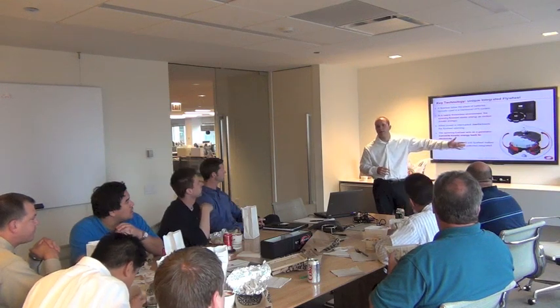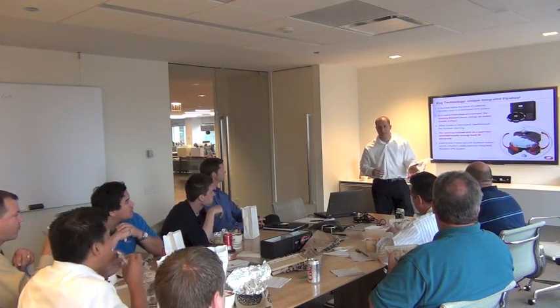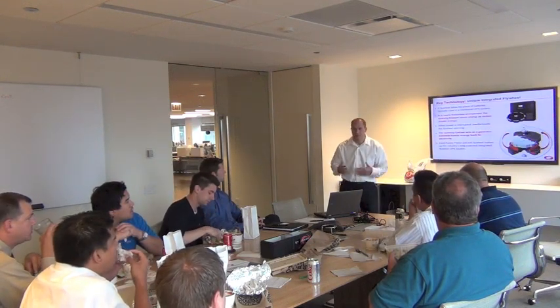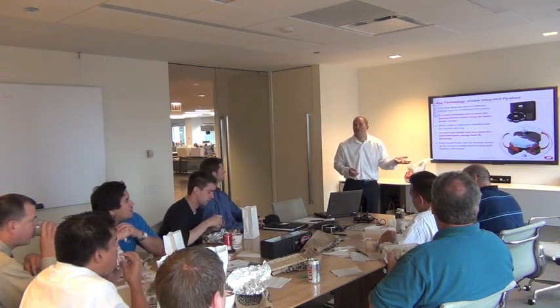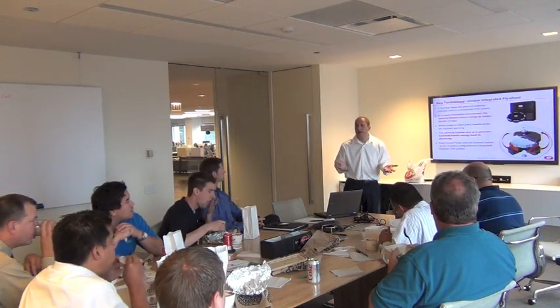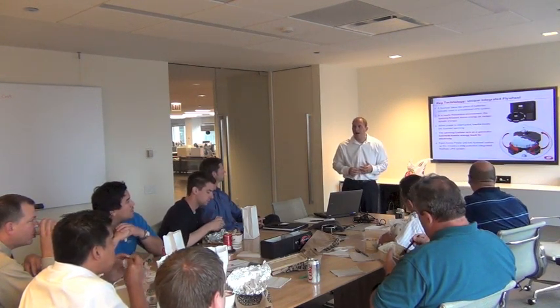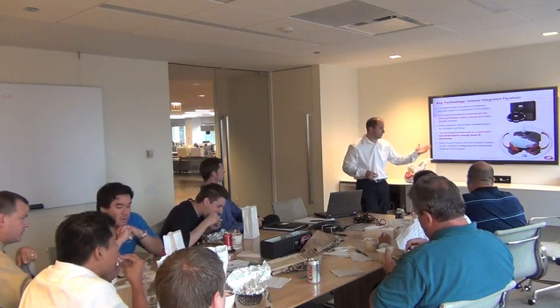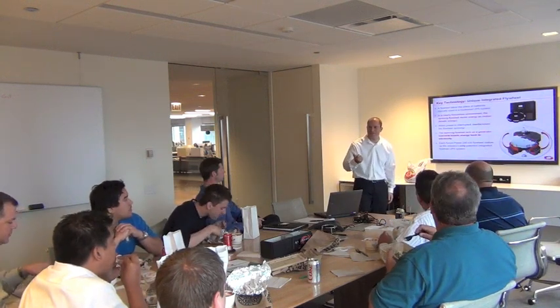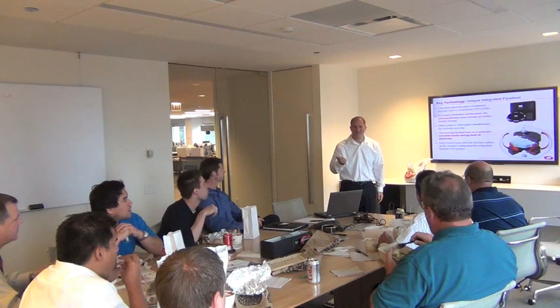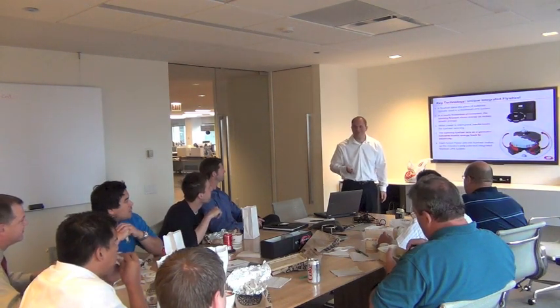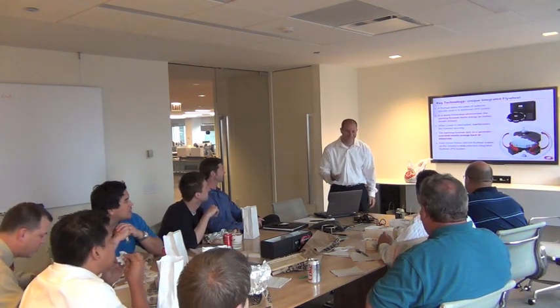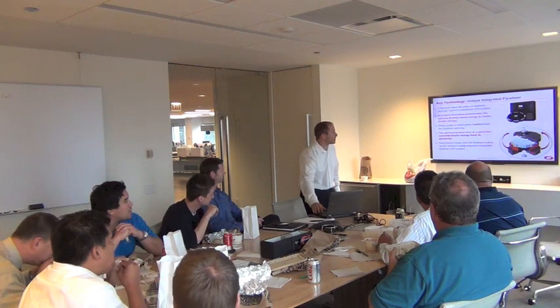Typically, it takes about 1250 to 1500 watts to maintain spin at 7,700 RPMs. So just to give you an idea how much that is, it's a 250 kilowatt wheel, 1500 watts. It's about a 99.5% efficient wheel. And I always kind of compare it to my wife's hair dryer, because she's got a hair dryer that says 1500 watts. And I'm like, I can spin a 600-pound wheel more efficiently than you can blow dry your hair. But it kind of gives you an idea of what the losses are.